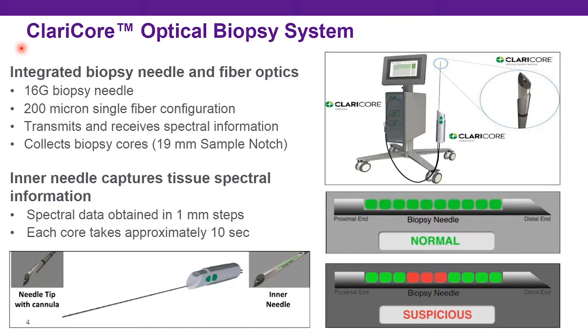The ClariCore optical biopsy system is a novel biopsy system developed to employ these optical characteristics at the time of needle biopsy. It uses a 16-gauge biopsy needle that contains a 200-micron optical fiber within the biopsy gun. The biopsy gun is very similar in appearance to a regular biopsy gun, but as an added component it contains a fiber within the needle that, as you place the needle into the tissue, both transmits and receives spectral information.